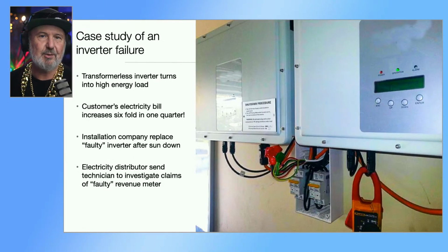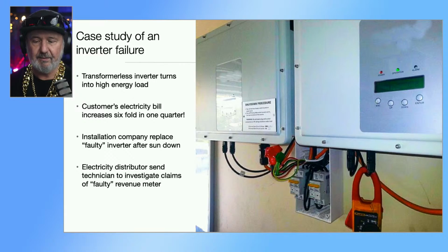Let's start with something I've actually shown once before, but for those who haven't seen it: why is it important, and why do we require equal potential bonding of PV arrays that are over 120 volts? It all comes down to things going wrong in the past. This is a case study from 2010. Prior to the 2012 edition of 5033, the PV array standard, there was no requirement for equal potential bonding of the conductive parts of a PV module or even the array frame itself. Systems were installed quite happily with no bonding at all on any conductive parts on the PV side. So this is a case study of what can happen under that scenario, and it's one of the contributing factors to why we required equal potential bonding of array frames.